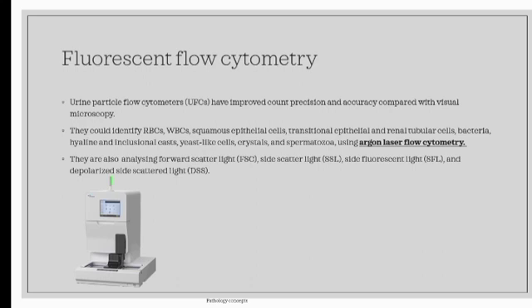The urine particle flow cytometers have improved count precision and accuracy compared with visual microscopy. They could identify RBCs, WBCs, squamous epithelial cells, transitional epithelial cells, renal tubular cells, bacterial cells, hyaline cast and inclusion cast, yeast-like cells, crystals, and spermatozoa using the argon laser flow cytometry. They are also analyzing the forward scatter light, side scatter light, side fluorescence light, and depolarized side scatter light.